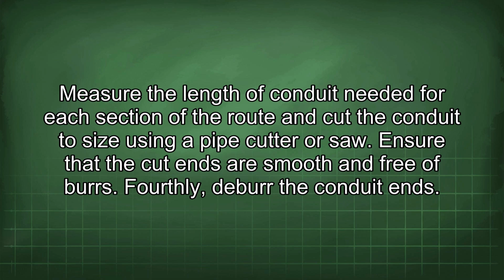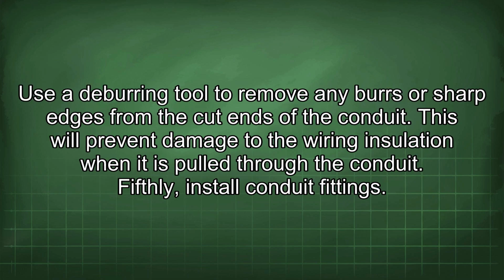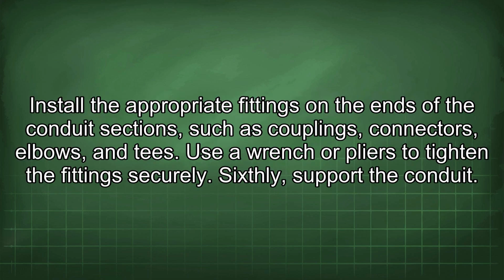Fourthly, deburr the conduit end. Use a deburring tool to remove any burrs or sharp edges from the cut ends of the conduit. This will prevent damage to the wiring insulation when it is pulled through the conduit. Fifthly, install conduit fittings. Install the appropriate fittings on the ends of the conduit sections, such as couplings, connectors, elbows, and tees. Use a wrench or pliers to tighten the fittings securely.